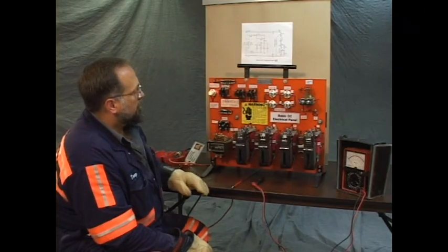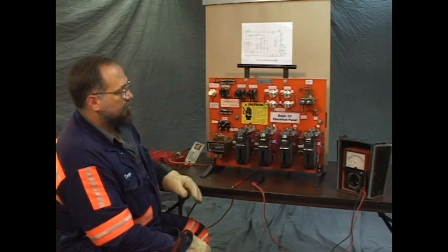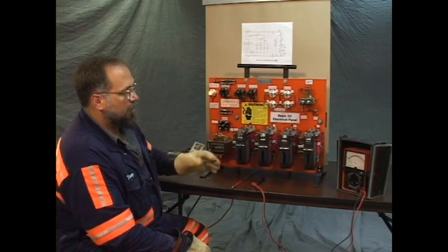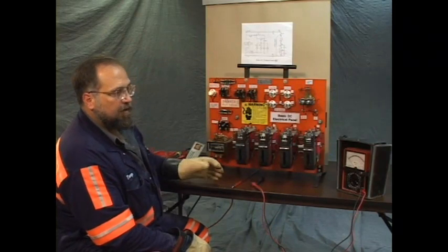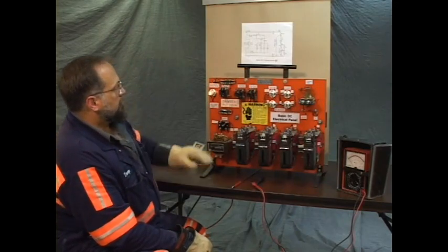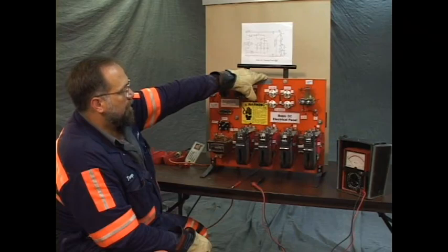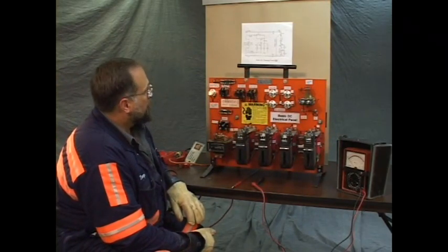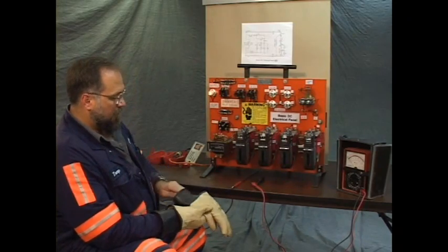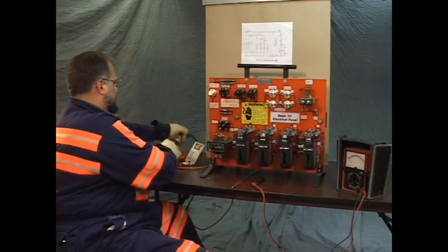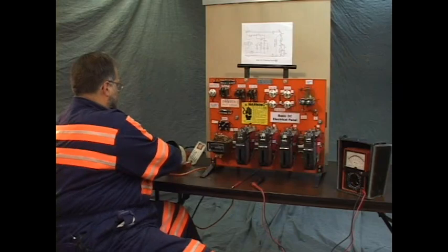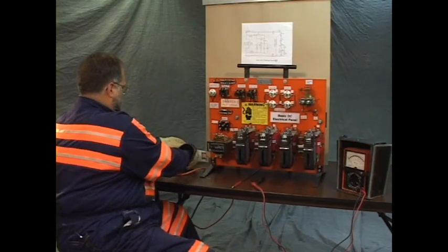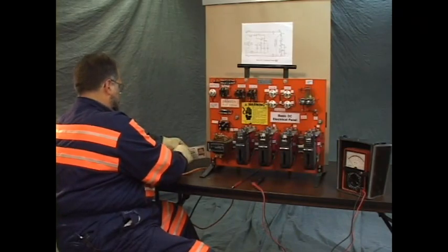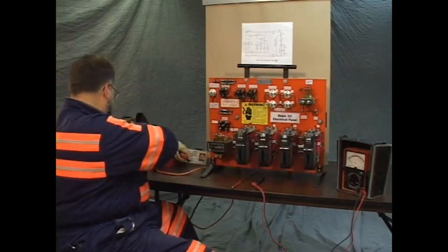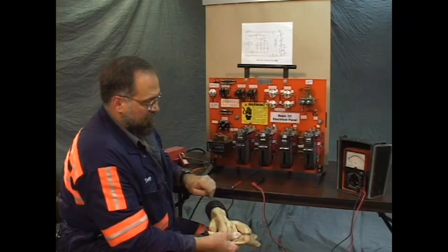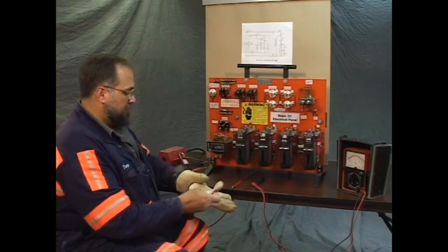These are momentary switches. They're only made or broken as long as you hold them in. So you're dependent upon part of the circuit to give you a holding circuit. Holding circuit means it'll keep the contactors closed and allow you to turn loose the switch. But we don't have that. Nor do we have any power to any portion of the motor. Okay, let's take the power off, lock and tag. We can test for power after we've locked and tagged.